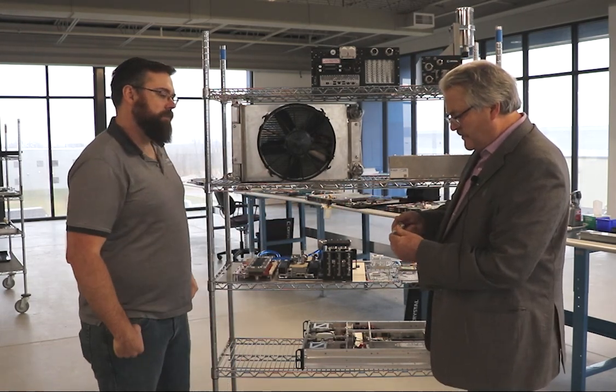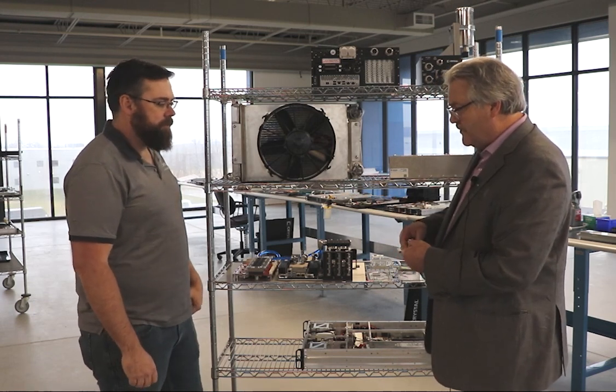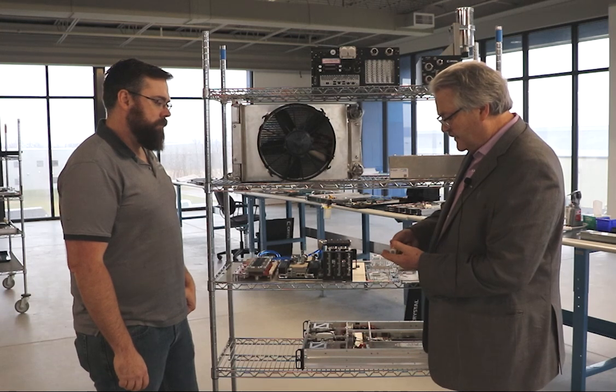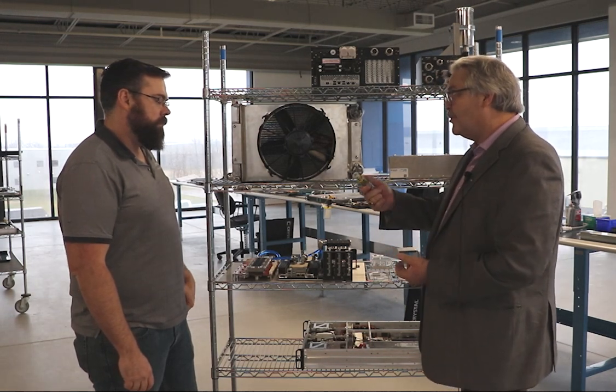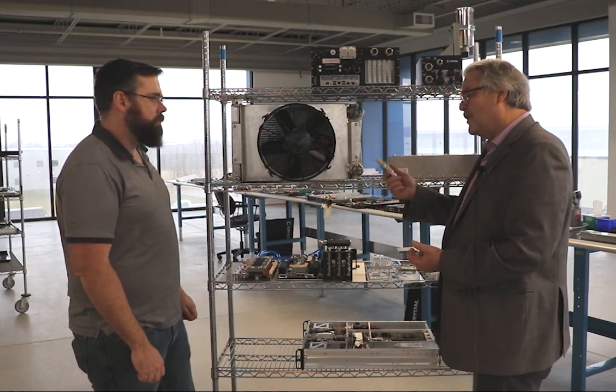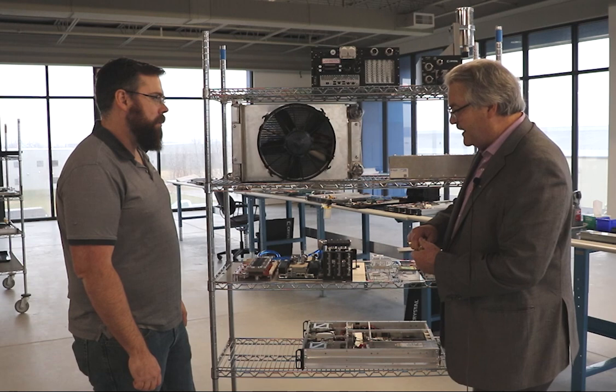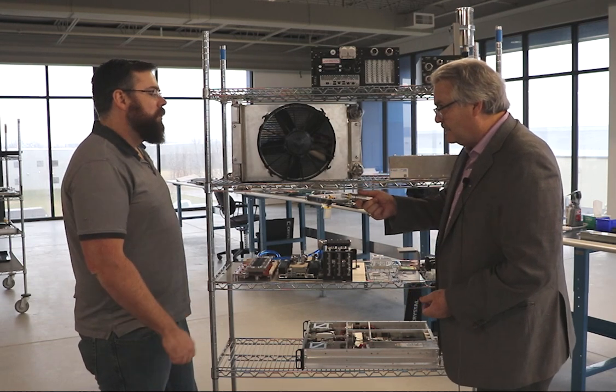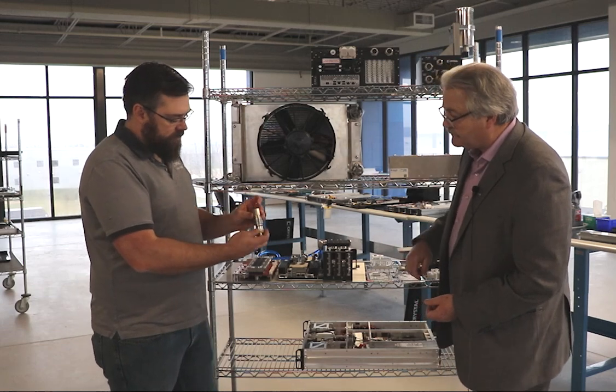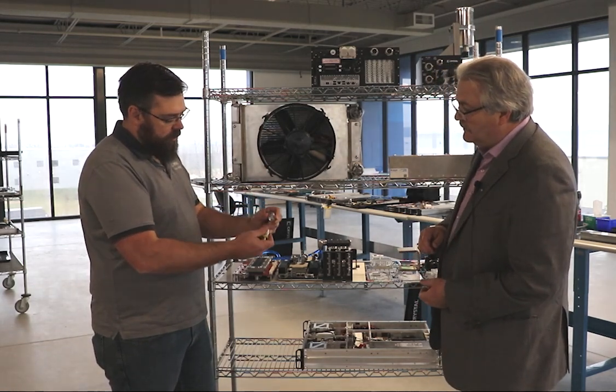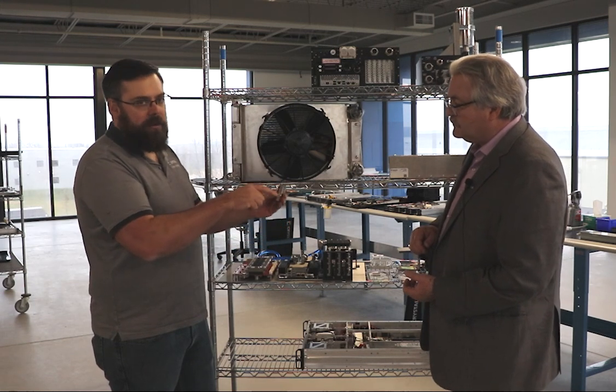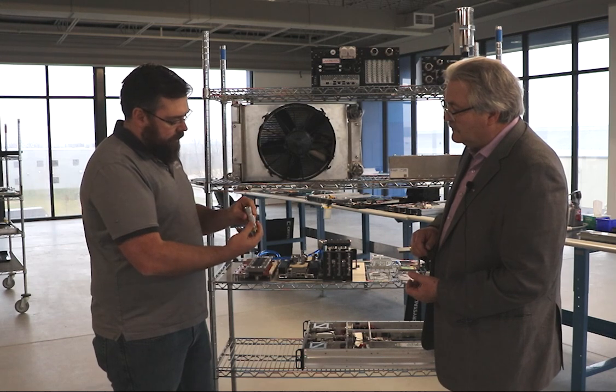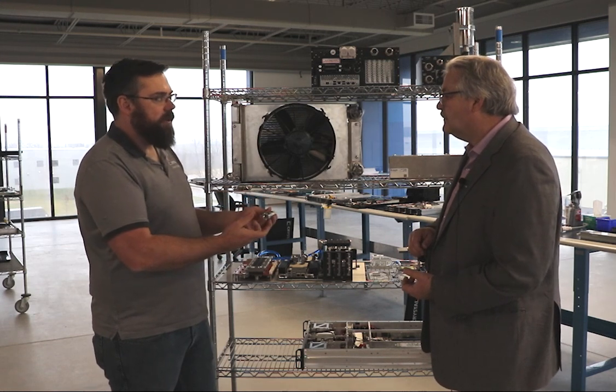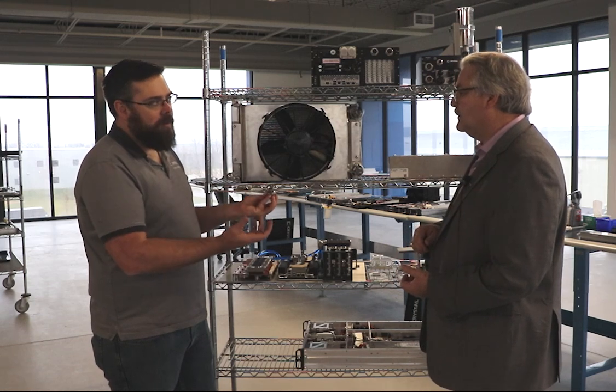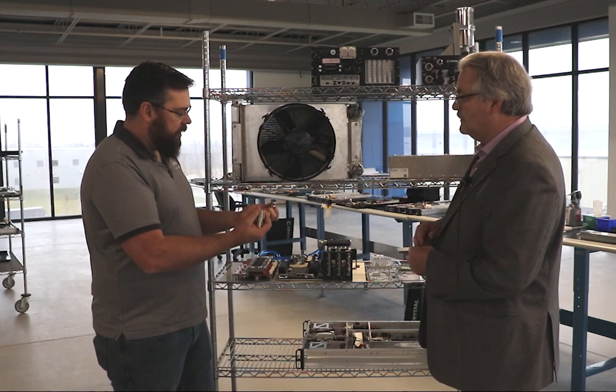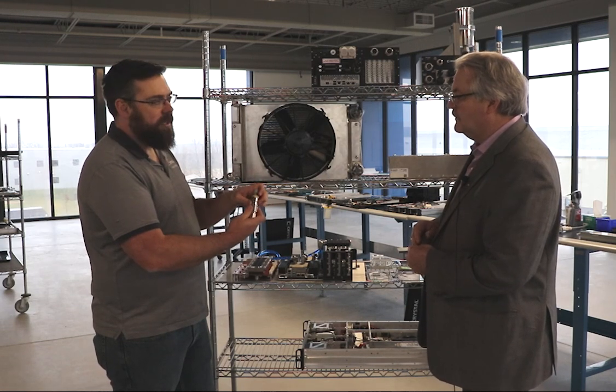So one of the big drawbacks on this is pressure drop, right? Correct, you give up a certain amount of pressure drop when you go with these fittings. What's different about this fitting versus what you might see in a rack environment with respect to leakage? One of the things you'd see here, talking about pressure drop, is that you're essentially creating a shutoff, and by doing that you're adding a bunch of right angle turns, which are high pressure drop environments. The difference between what you'd see here and on a rack is that rack fittings are generally designed to be high flow, low pressure drop. We're willing to accommodate that higher pressure drop just to make sure we're not going to see leaks inside the system or leaks in the field.